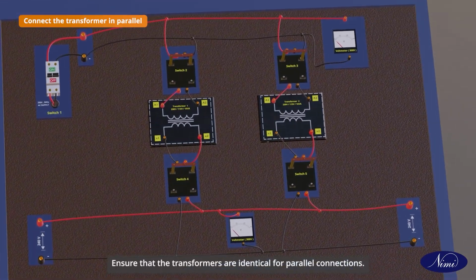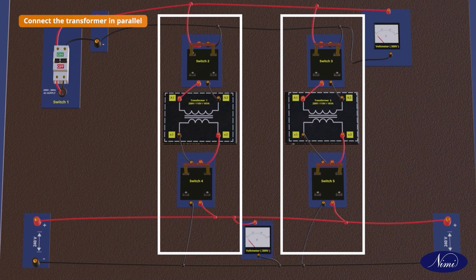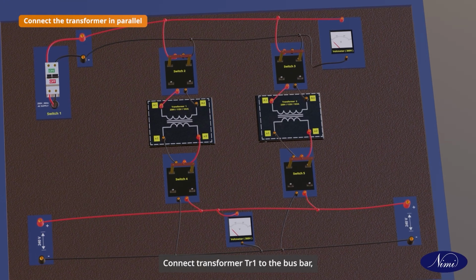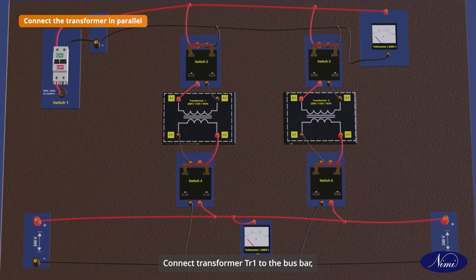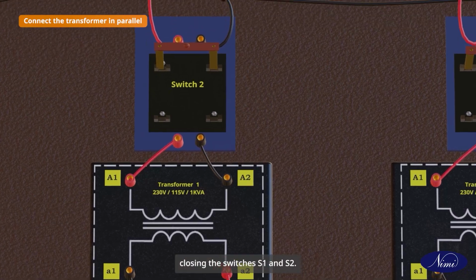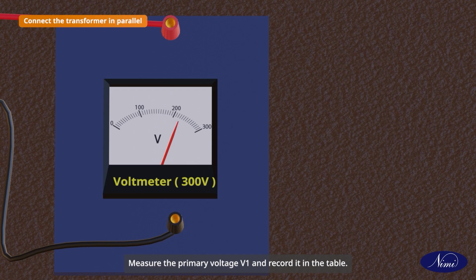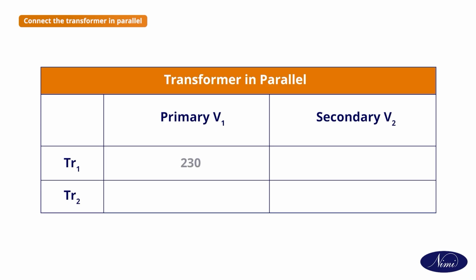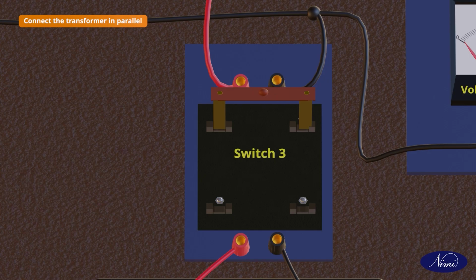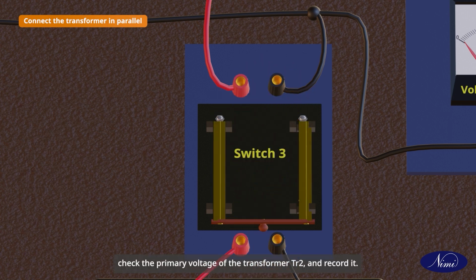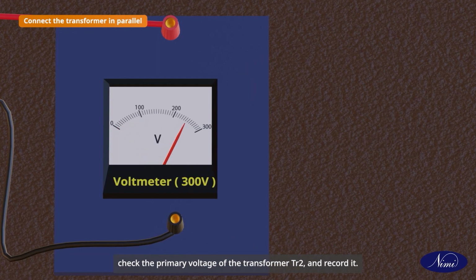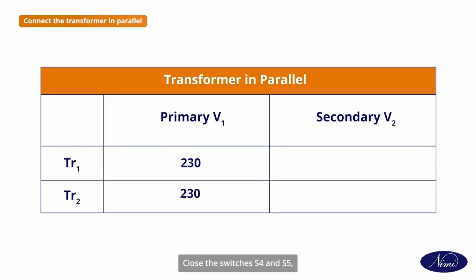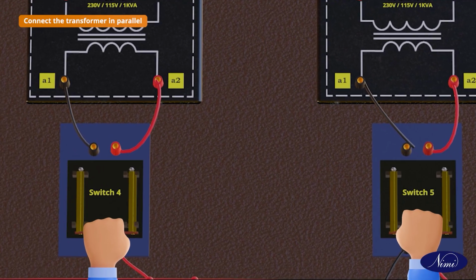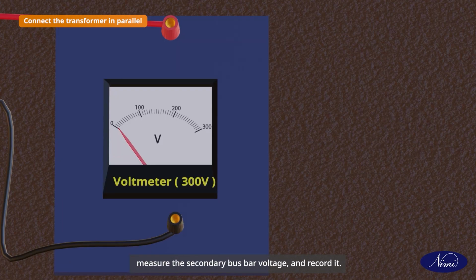Ensure that the transformers are identical for parallel connections. Connect transformer TR1 to the bus bar, closing the switches S1 and S2. Measure the primary voltage V1 and record it in the table. Close the switch S3, measure the primary voltage of the transformer TR2 and record it. Close the switches S4 and S5. Measure the secondary bus bar voltage and record it.